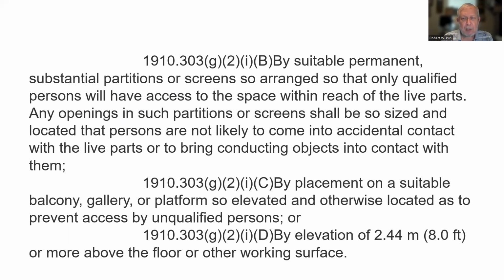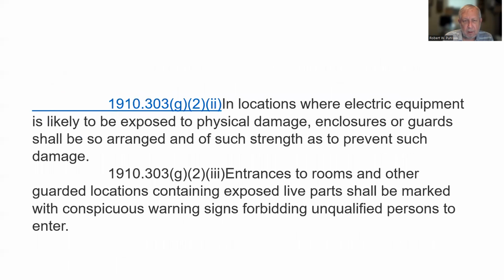Any openings in such partitions or screens shall be so sized and located that persons are not likely to come into accidental contact with the live parts or to bring conducting objects into contact with them. By placement on a suitable balcony, gallery, or platform so elevated and otherwise located as to prevent access by unqualified persons, or by elevation of 8 feet or more above the floor or other working surface.